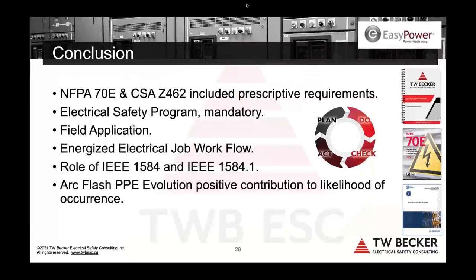All right. So I moved very fast today because I wanted to open up the floor. So just to bring things to conclusion, NFPA 70E and Z462 are prescriptive standards. They have prescriptive requirements in them. And I mentioned earlier, the electrical safety program is a mandatory requirement. And I don't know why companies don't have programs, because 70E, right in Article 110, says the employer shall document, develop, implement an electrical safety program as a component of their overall occupational health and safety management system. So 70E and Z462, right away, that's the first thing they say.